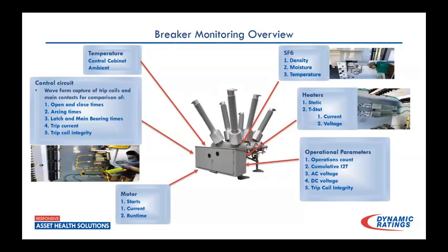Again, when we get into monitoring, you would also need to look at motors. That would be a huge thing, to understand how that motor's running, especially when you come to pneumatic and hydraulic type systems, to understand, do we have leaks developing in these stored energy systems? Are motors running when they're supposed to on closes for springs? Are we seeing that motor run that's causing a charge? SF6 we're all aware of, and that should be something that everybody is taking a close look at.